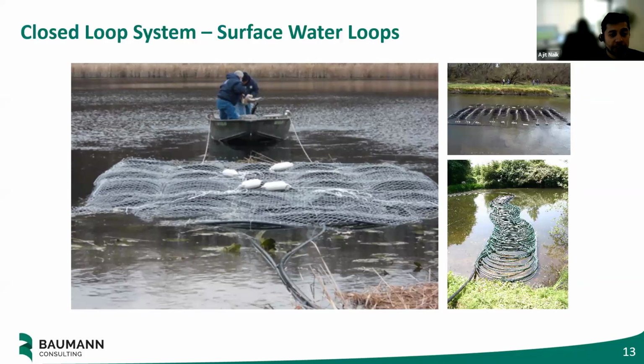That brings us to closed loop systems. As you can guess, they don't draw water from nature and don't discharge water to nature. They have a fixed amount of water to begin with that circulates throughout the cycle and never leaves the system, so it never goes into nature and never comes out of nature. That means we have to put this pipe somewhere, a big long length of pipe that we run water through, and it has to heat up or cool down and exchange with the ground.